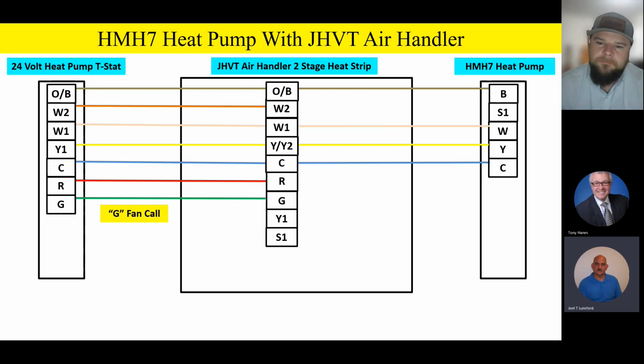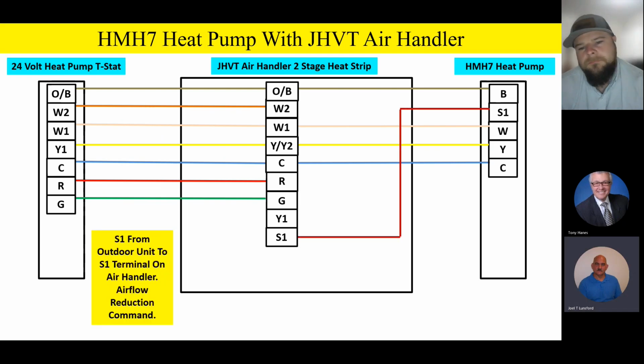Now you're going to notice something. Y1 terminal on the air handler is not used at all. But we are going to take that S1 from the terminal board on the air handler and take it outside to S1. So we don't have a relay kit, but we do have an S1 terminal on that board that's going to go outside. Now, be sure and look at the install information because the install guide, I think it's on page 13, but you can double check on that.